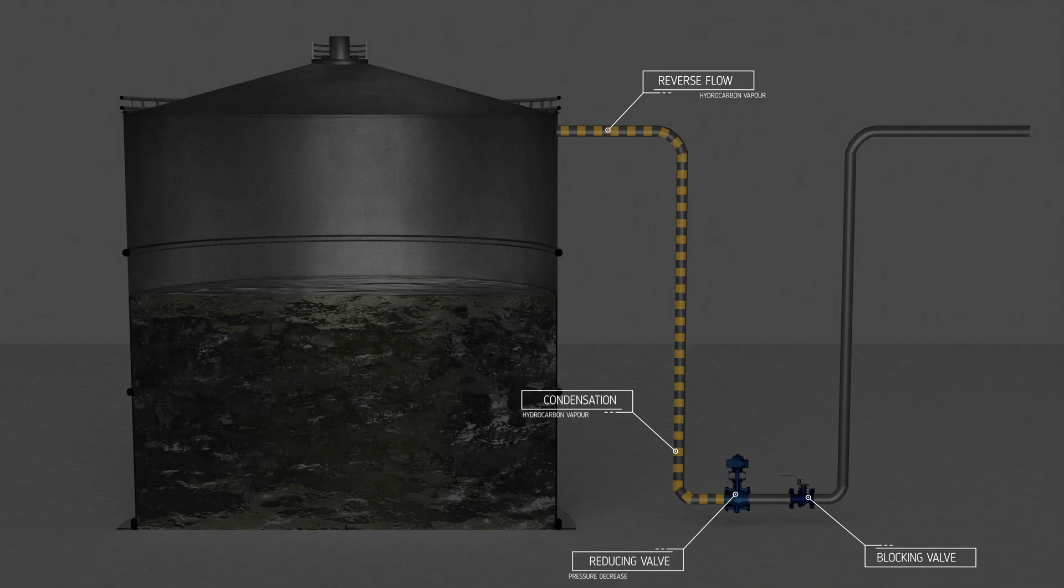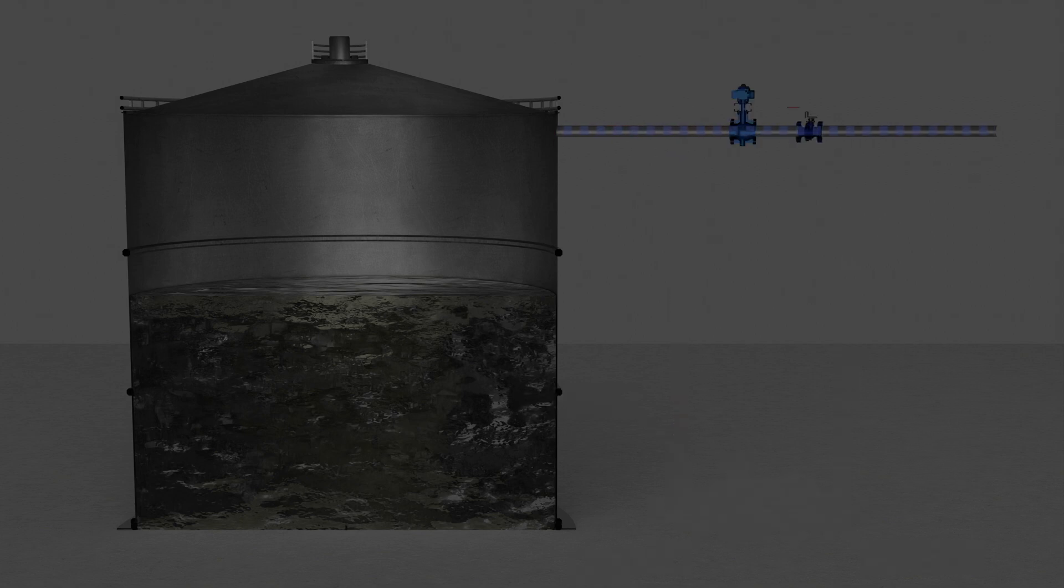Also, the reducing valve of the nitrogen supply was installed at ground level. Hydrocarbon vapor condensed in the vertical section of the line and effectively isolated the tank from the nitrogen blanketing. The reducing valve should have been installed at roof height. Check your tanks, there may be more like this one.